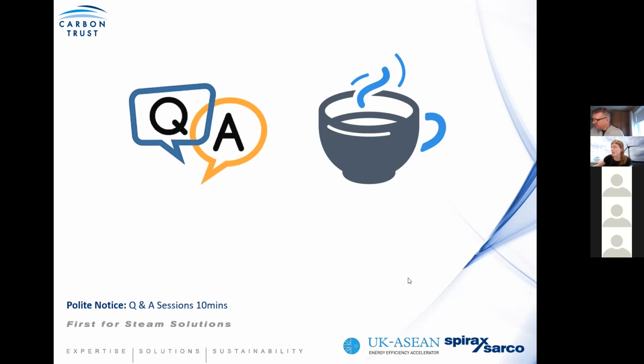So Ray, just on the steam systems, we might have covered this before, but just to ensure this has been covered, how often should the steam trap surveys be undertaken? What's the recommended frequency? At least once per year, and at least every 6 months if they're critical applications. Okay, thank you.